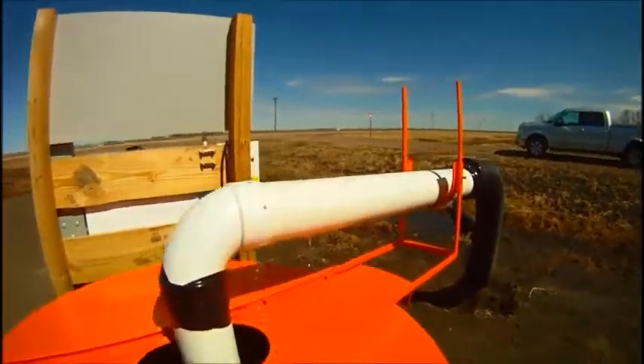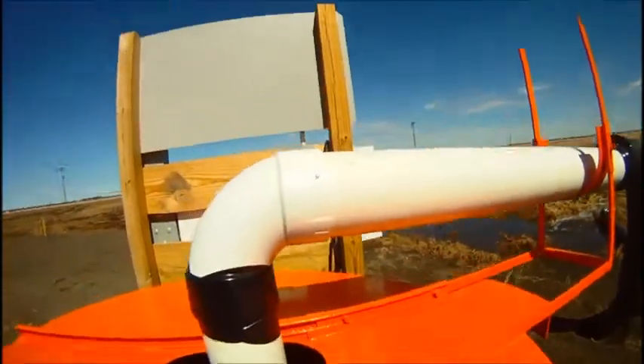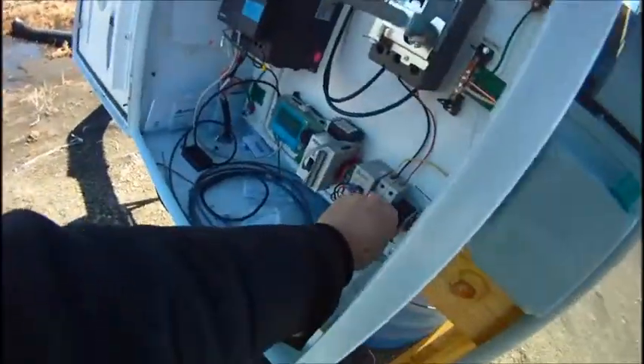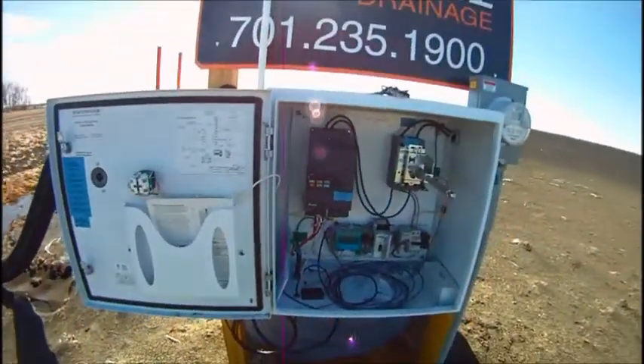You can already hear it running. We'll watch how far down she goes. Make sure we see that the bottom of that tube is there. You see the bottom of the tube. We're going to shut it down. So we just ran it dry. You never want to run your pump dry. Steps to change that tube out. So you can see the bottom of that tube right there.